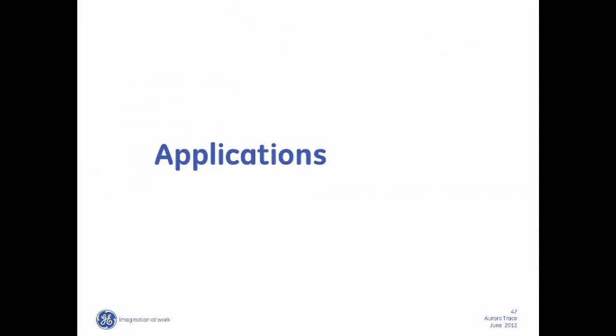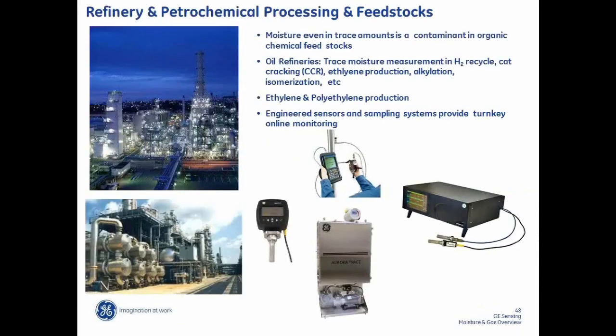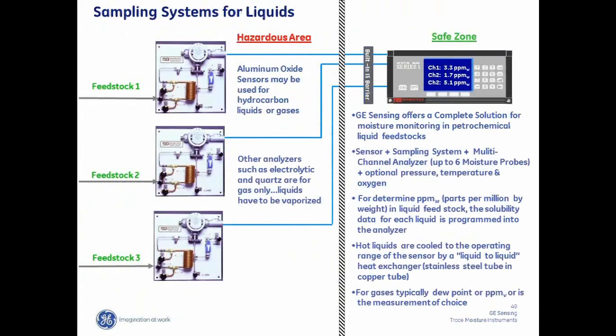I'm just going to run through the applications pretty quick, as we're starting to get close to the end point here. But a lot of what we sell is applied to refineries and petrochemical. These are the feedstocks, but we also get involved in catalytic cracking, or CCR, on the H2 recycle gas, ethylene production, alkylation and isomerization. And very often these systems are put together with fairly elaborate sampling systems. For liquids, for example, on these sampling systems, we have stainless steel tubing inside a copper tube, and fluid is run through the copper tube to cool the gas sample, or the liquid sample, prior to the sensor.